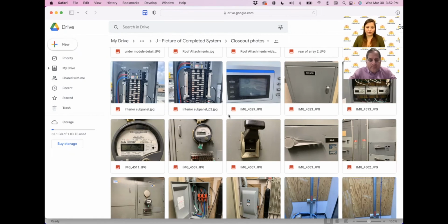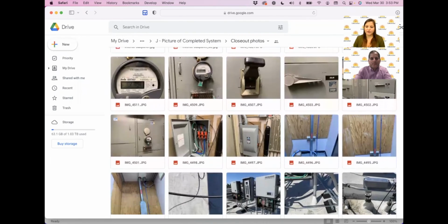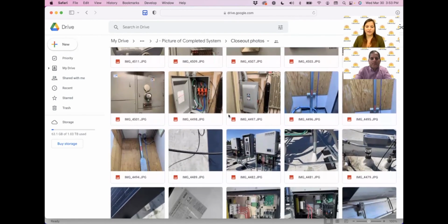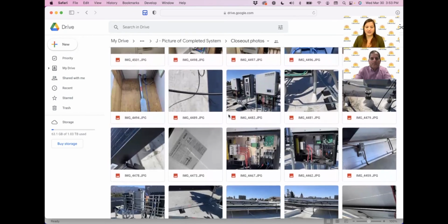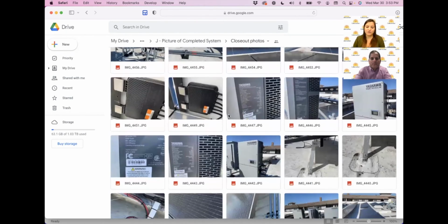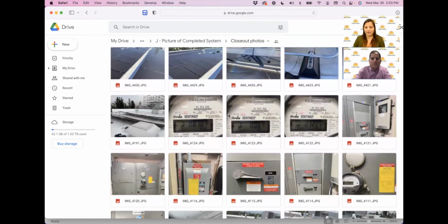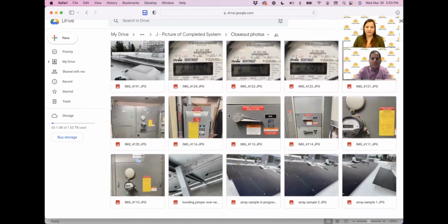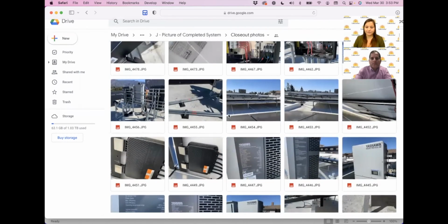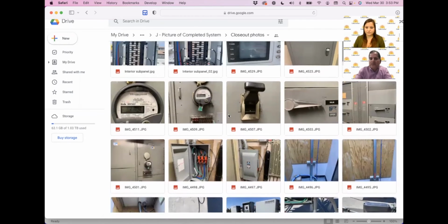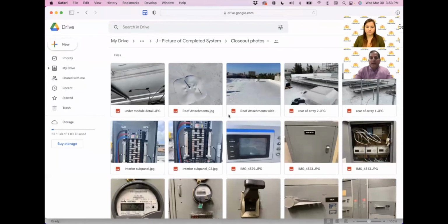So along with our commissioning report, we have a photo requirement document that we send out to the contractors. And it typically consists of around 70 photos or so, where we just look at every part of the solar system. So wiring under the panels, the exact panels, the inverters, the internal wiring, and so forth. Just to make sure that everything is built, these photos get reviewed by one of our third-party engineers, just to confirm everything is A-okay before moving forward. Great. And so it's fantastic to have documentation of the model number and which inverter was installed and where it's actually located. All that gets reflected here, and that's part of the as-built.